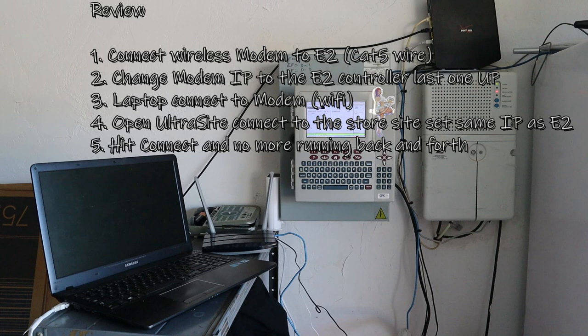So to review: number 1, connect the wireless modem to the E2. Number 2, change the modem IP to the E2 controller's, last one up or down. Number 3, laptop connect to the modem, wirelessly, just to the actual modem wireless. And then number 4, open Ultrasite, connect to the E2, make sure on the E2 that the site is the same IP as the E2 controller itself. And number 5, hit connect, and no more running back and forth in the sales floor trying to figure out if it's correct or bypassing something on. You could use a handheld, but you know, have fun with this.